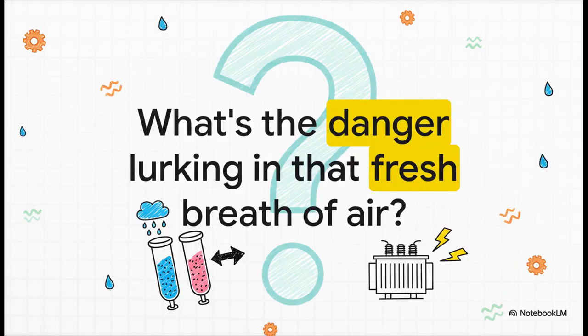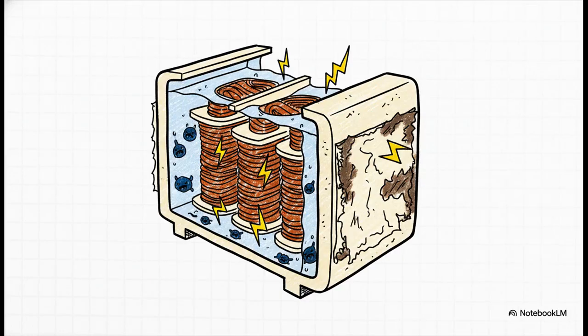So this whole breathing thing is completely normal, totally necessary for the transformer to function. But here's the catch. Every single time it takes one of those breaths, it's potentially inhaling a silent killer. So what could be lurking in just a simple breath of fresh air that's so dangerous? The enemy? It's just moisture. Simple H2O. But when that water vapor gets inside the transformer's oil, it is absolutely catastrophic.